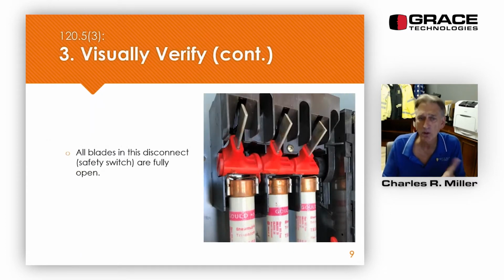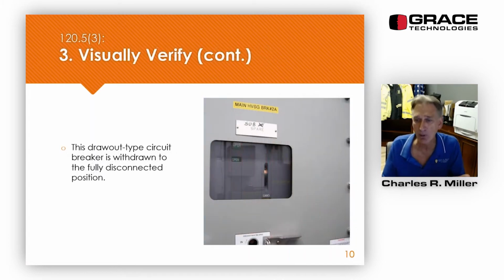All right, so here's an example. We open the disconnect or safety switch. We see that all 3 blades in this case are fully withdrawn. They're not connected. Or here's an example of switchgear with a rack-in, rack-out, draw-in, draw-out type circuit breaker. Besides it saying open, we also know that it's not able to connect because it is right at the door. When it's able to connect, it's typically 18 to 24 inches inside the cabinet, inside the front of the door. Now this switchgear has a window. Not all switchgear or breakers like this have windows, but this was easy to see, especially easy to see that it says open.